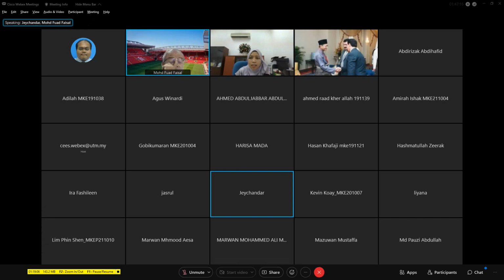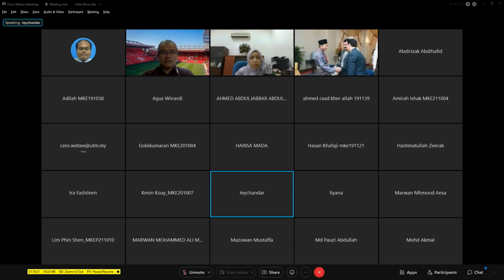Yes. Actually, I'm a contractor for LRT Line 3. We are doing a few stations. Previously we were also involved in LRT Line 2. Now, when this job was awarded, they never implemented this EMC compliance before. But now all our equipment, all our panels, all our sensors, they said must be EMC compliant. So it's a requirement for all our LRT substations, 33 kV and 11 kV. Just wondering, previously when they did Line 1 and Line 2, how did they mitigate this? Was there no mitigation, or were they doing it?